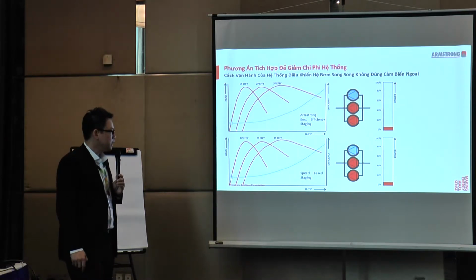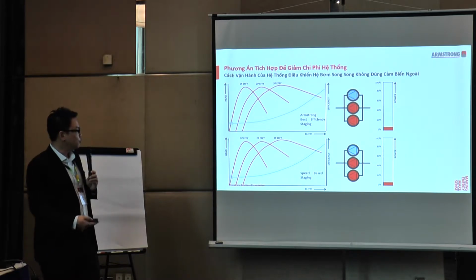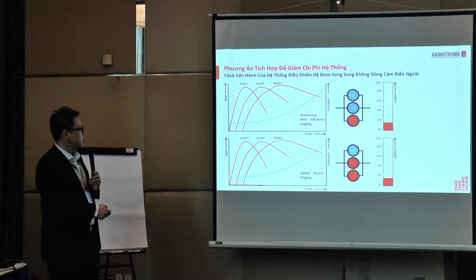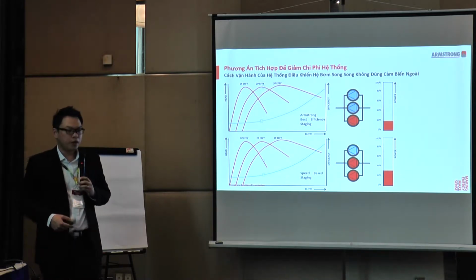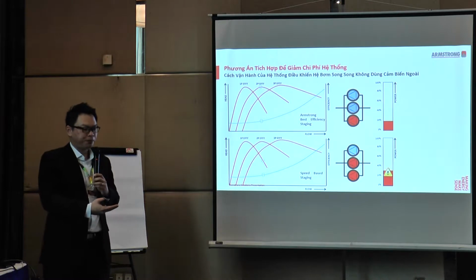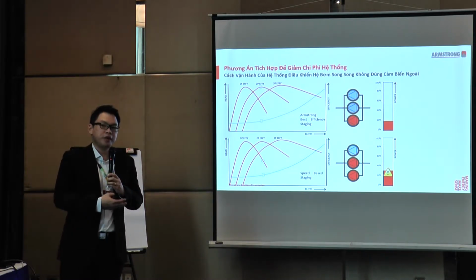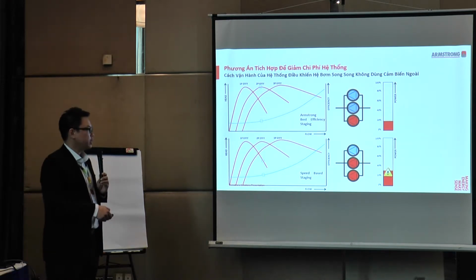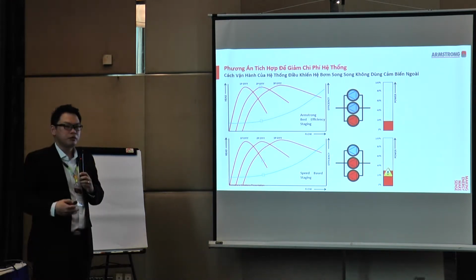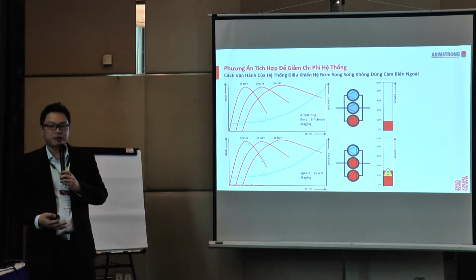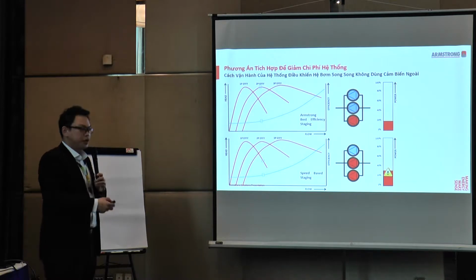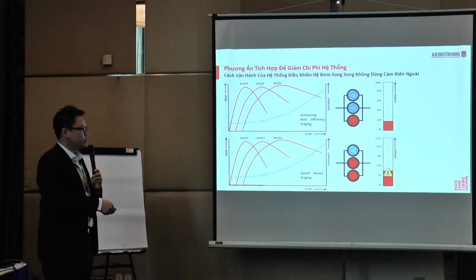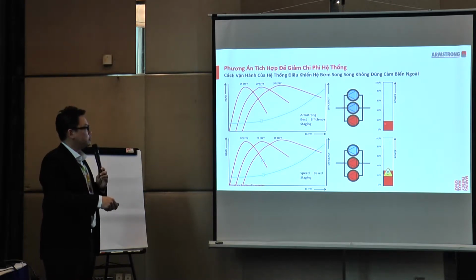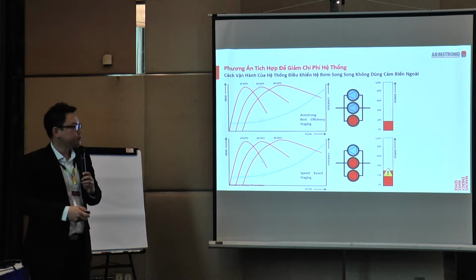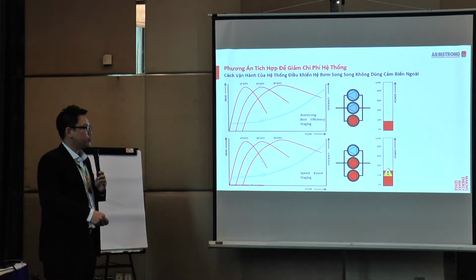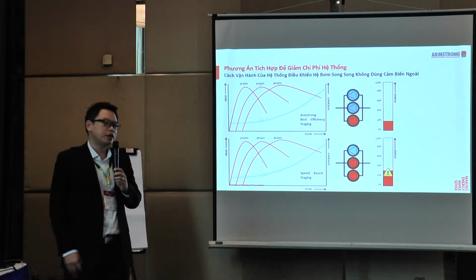At the start, yes, there is movement. At this juncture, we start to turn on the second pump, but the traditional speed-based BAS control is still operating on the single pump. It will perhaps run until 90 to 95% of the maximum speed. So even though we are already running 2 pumps, we are only consuming 18% of the power, whereas the speed-based control is already consuming 30% of the power.